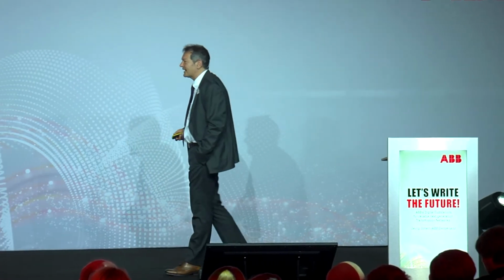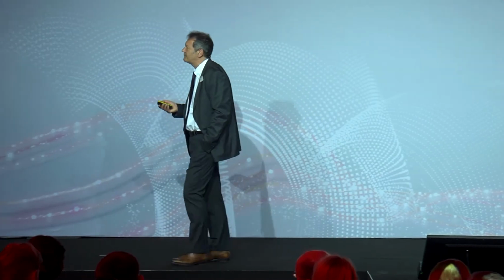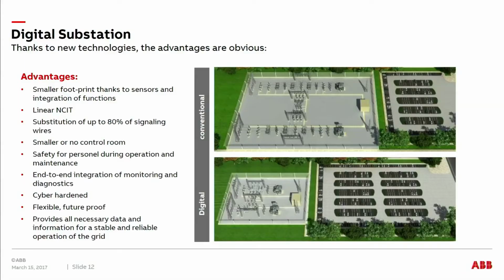You can make very accurate digital signals available in the grid wherever needed. This is a transformation of how the architecture of the future substation looks. This means not only clever new technologies, but also visible impact. Here's a picture of a conventional, traditional air-insulated substation, which needs a lot of space and is bulky. The digital substation, also air-insulated, will use less than 50% of the footprint, meaning you could place future substations in locations where today it's not possible due to space. It also means you'll be able to change the topology of the network to adapt to new opportunities and features you don't have today.